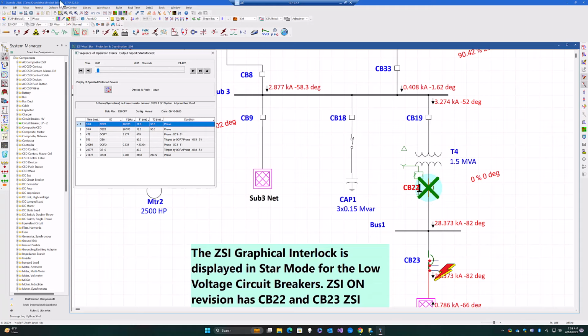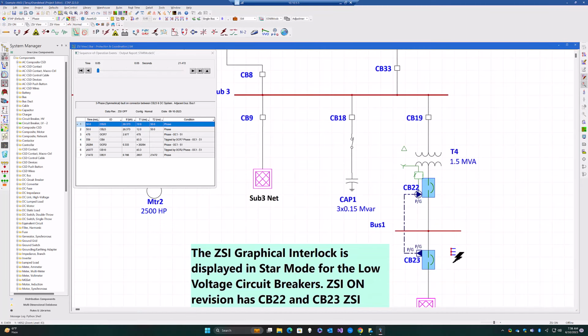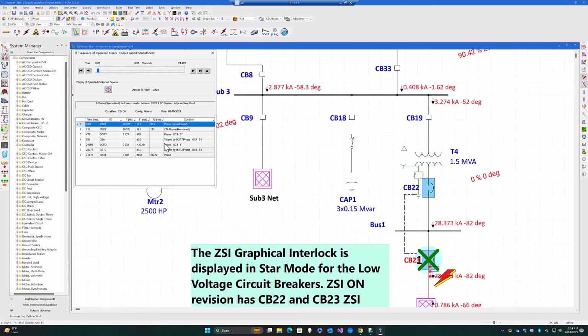If there were other loads connected to bus 1, this would not be an ideal coordination setup for us. So if we go to ZSI on and we go ahead and apply the same fault again, in this case we can see CB23 is tripping first, then followed by CB22, which is being restrained by the ZSI wiring that we have applied. So this is now giving us better selectivity with the same settings that we have for 22 and 23. So the ZSI is impactful in terms of providing selectivity, as well as offering arc flash mitigation techniques, especially for low voltage systems.